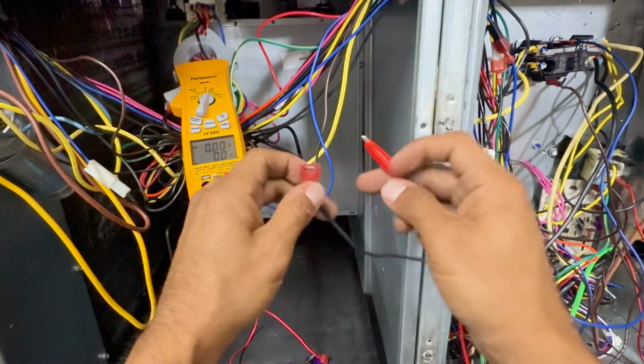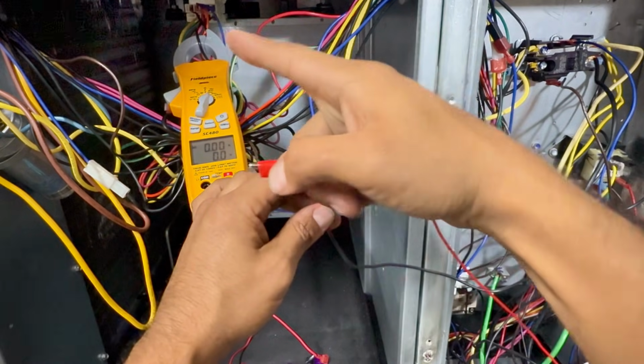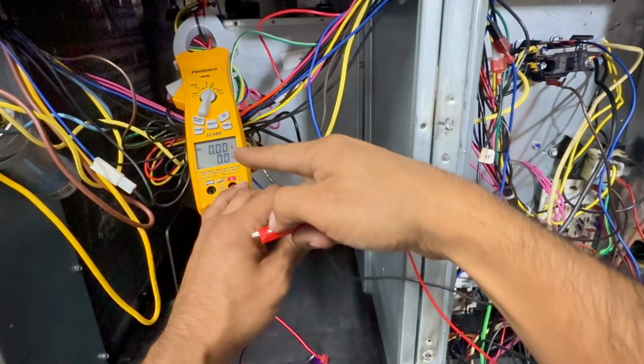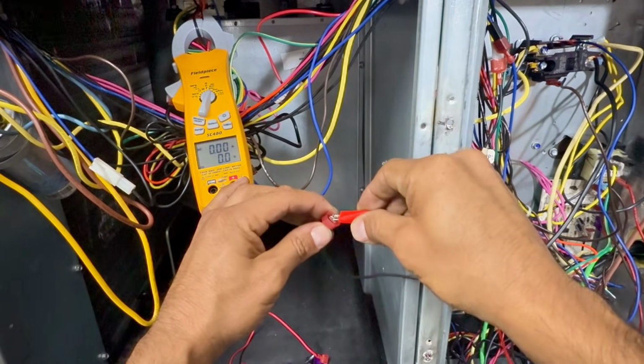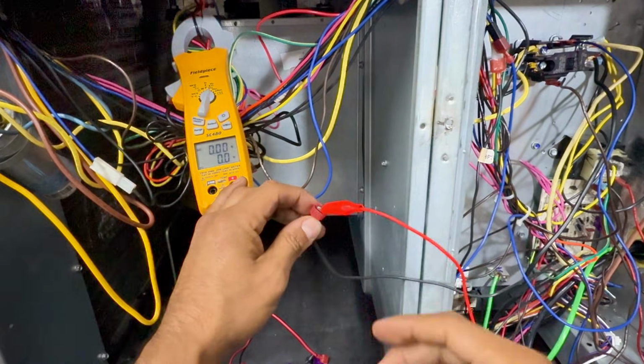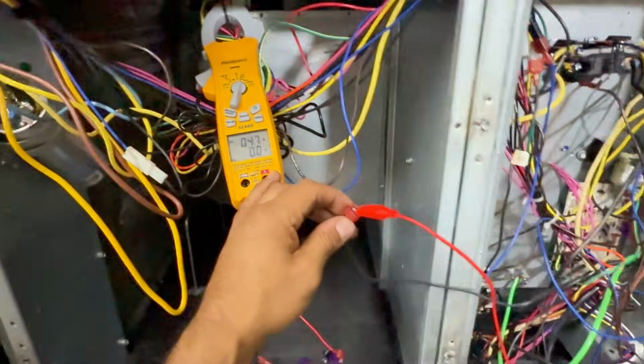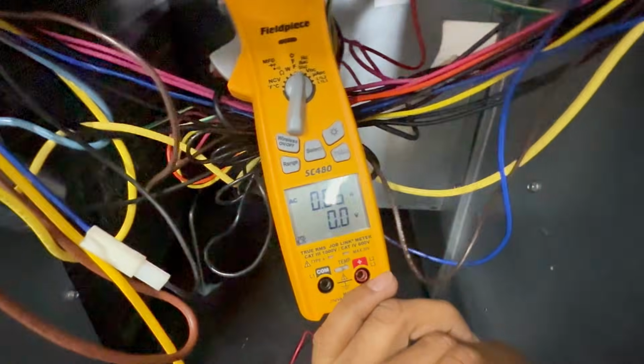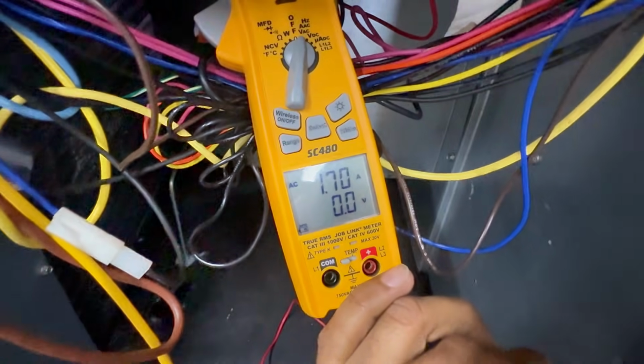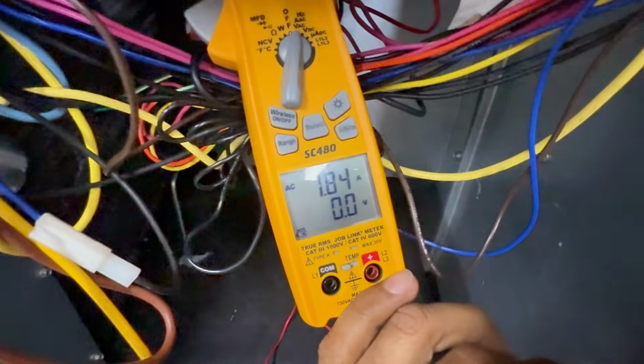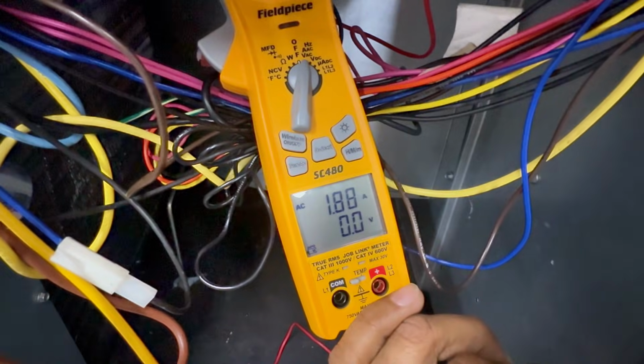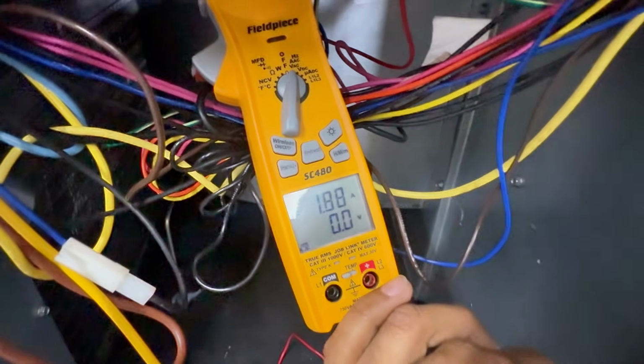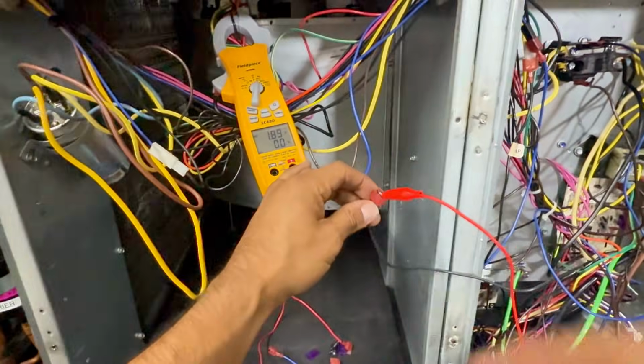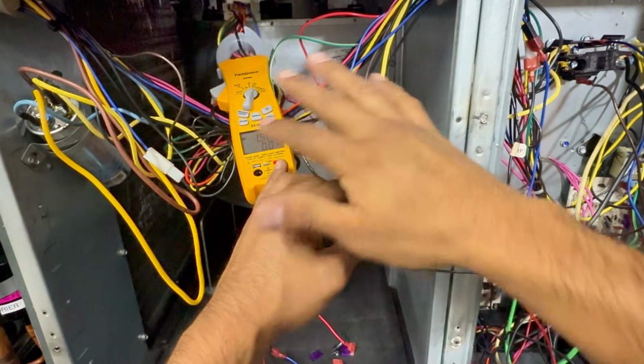So once I send 24 volts to that speed tap, the 24 volts part of it is gonna turn on and you're gonna see I'm gonna get some amps. Okay, give it a second. Right there, you see? So it's pulling about 1.8 amps, 1.9. So it's doing some work and I can feel some of the air, right, pulling in.